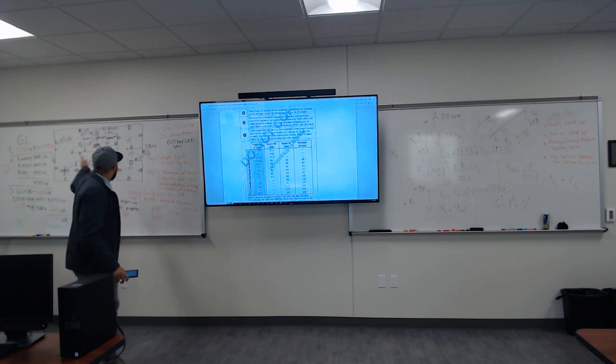Now I have 100. I was like, man, that's kind of high. That's too high. All right. 170 and a half amps is what is being required to serve this house. That's at 1,500 or 1,600 square feet. Now we need to figure out what size service conductor, then the size main breaker, and everything else.